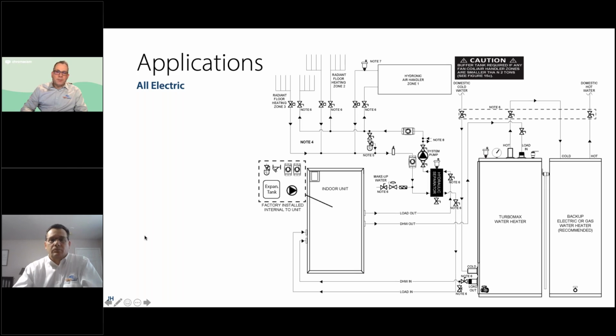We have the TurboMax indirect water heater you can see on the right, and we do recommend a backup water heater. In a lot of cases, we'll have high hot water loads, and we also are using that tank for defrost. So the backup water heater is just a nice, inexpensive adder that sort of completes the system.